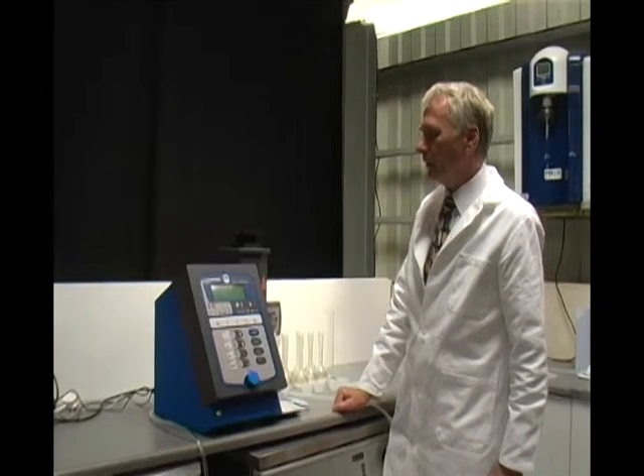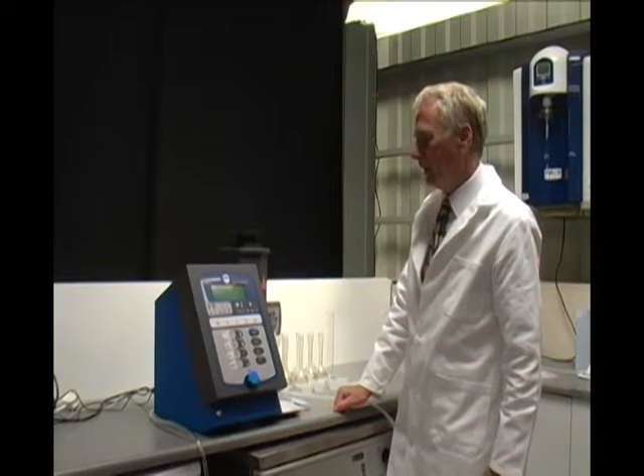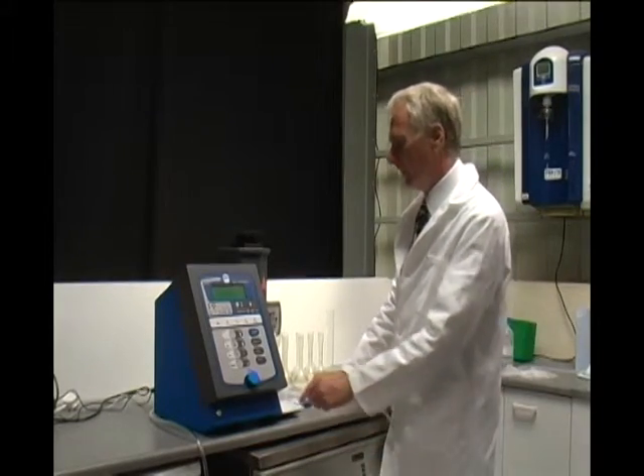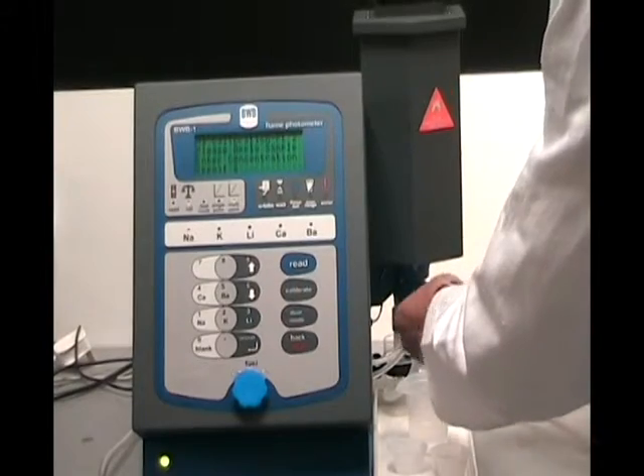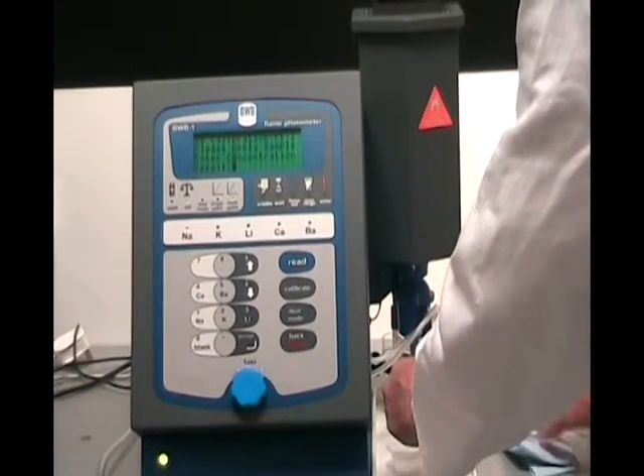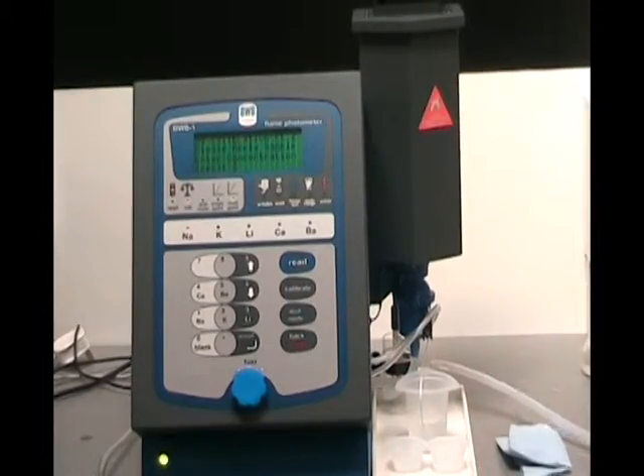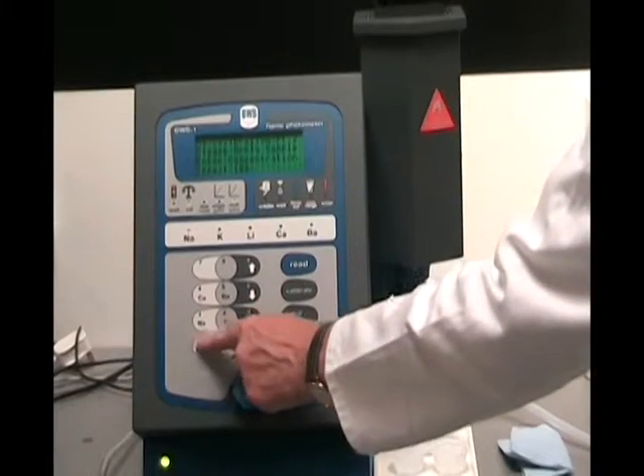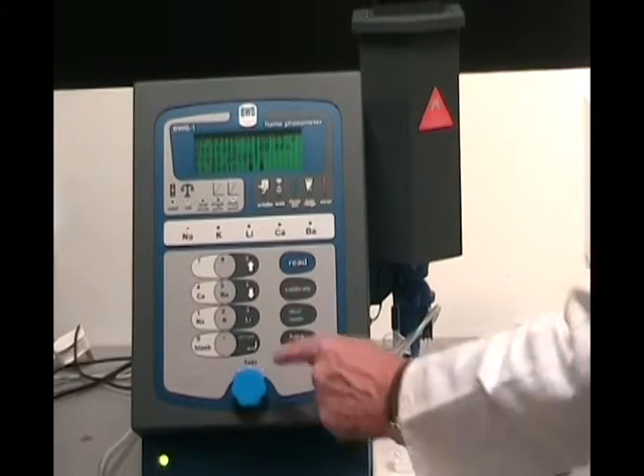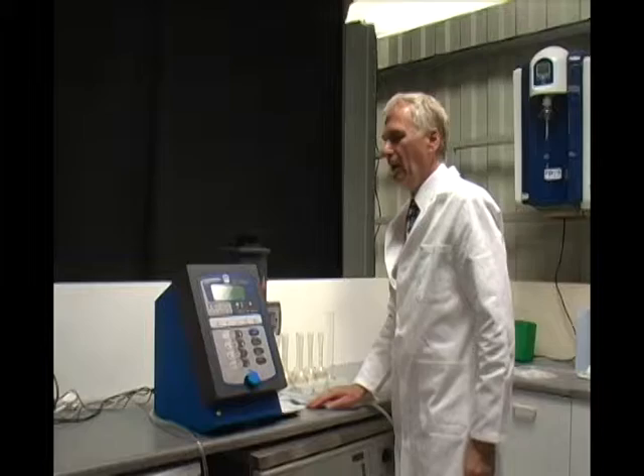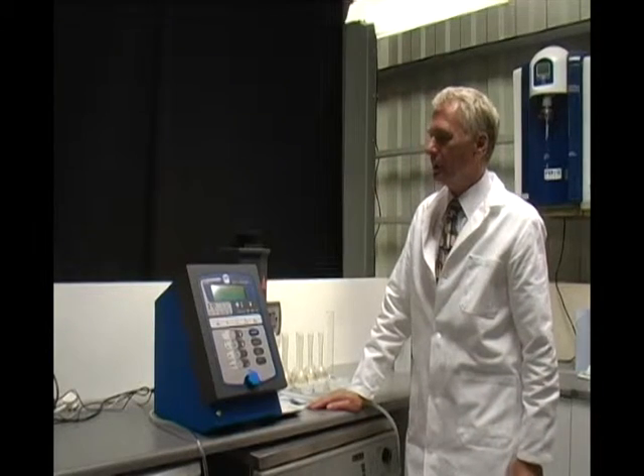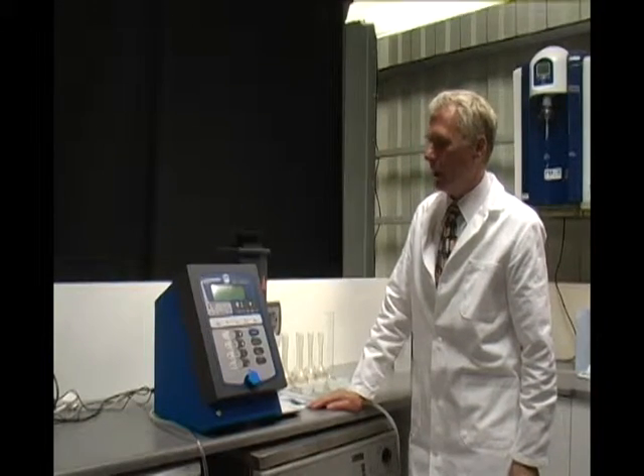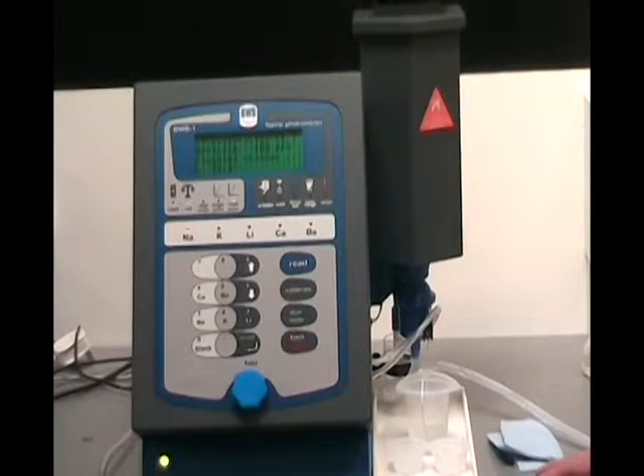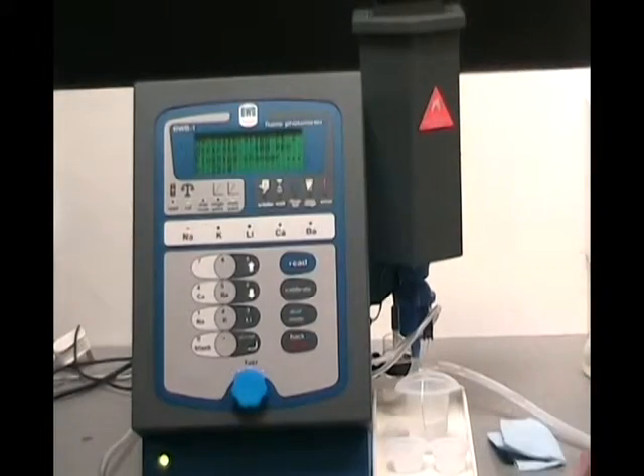That is now taking its reading and will be finished in just a moment. There we are, that's the first reading taken. I will now put it into the 100 ppm solution and say I'm using 100 ppm, press accept, go through exactly the same sequence of flushing the chamber and taking the reading. Once again you can see the icon where it's rising and going to a flat level to indicate that we have a nice reading.